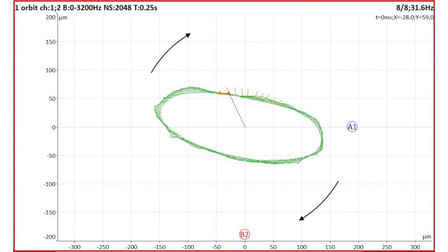Now you certainly would ask me why the keyphasors are not in the same place. It is because of the data. It is the run-up record. That is why the positions are shorter and shorter. You can see the shaft position is 0 microns on both axes. We do not use the DC channels, just only the AC channels. It means that DC part was removed.